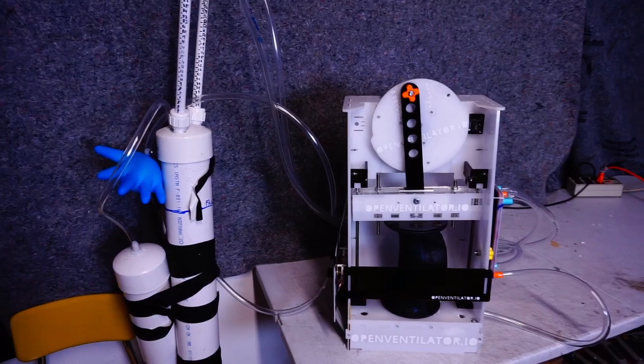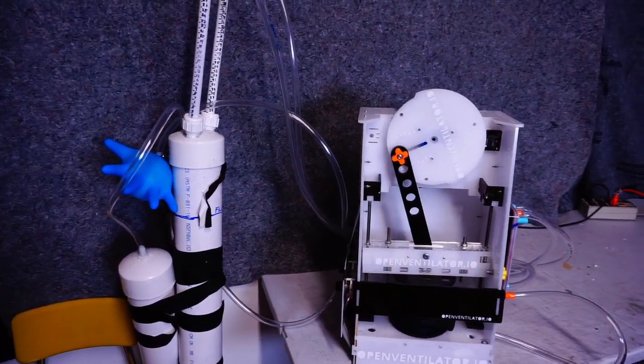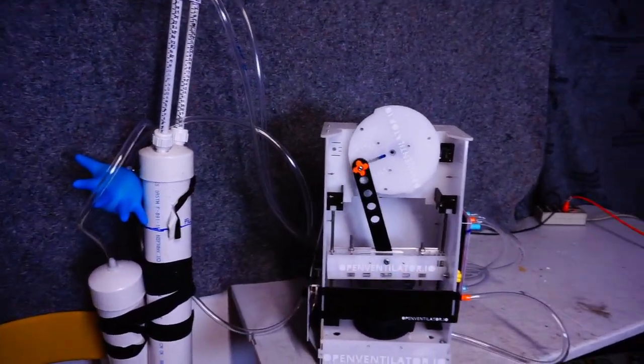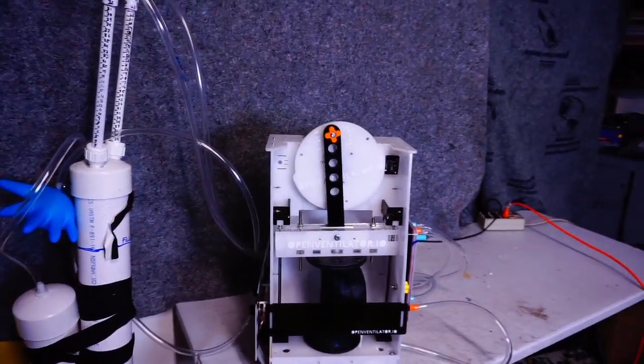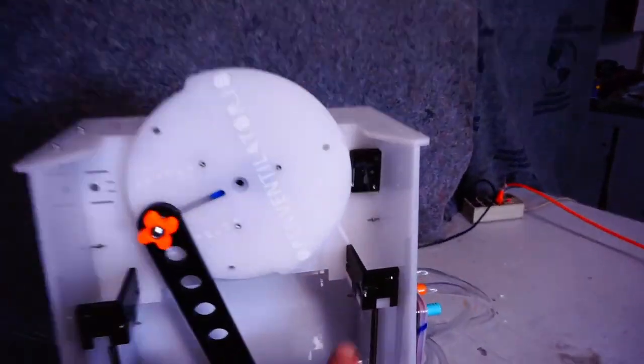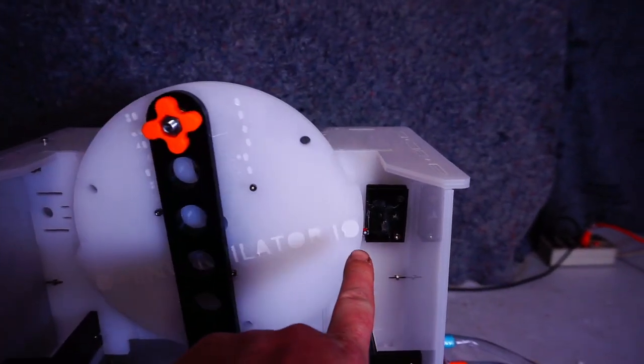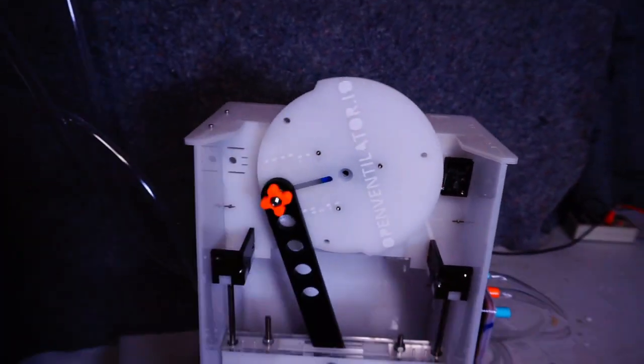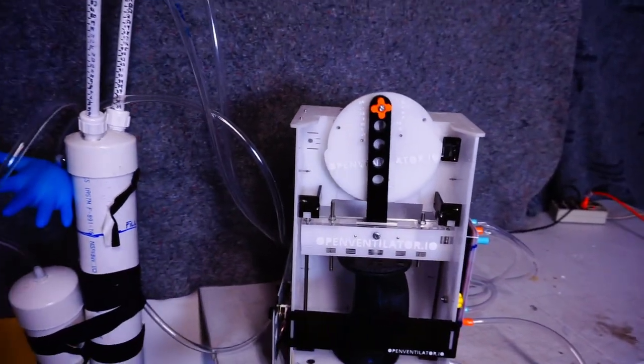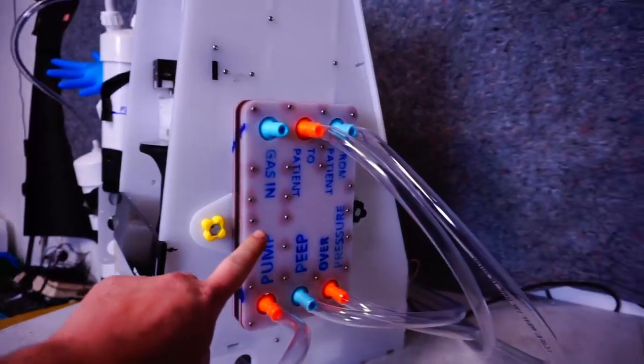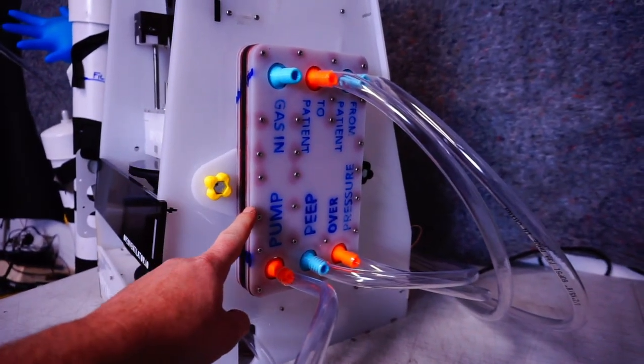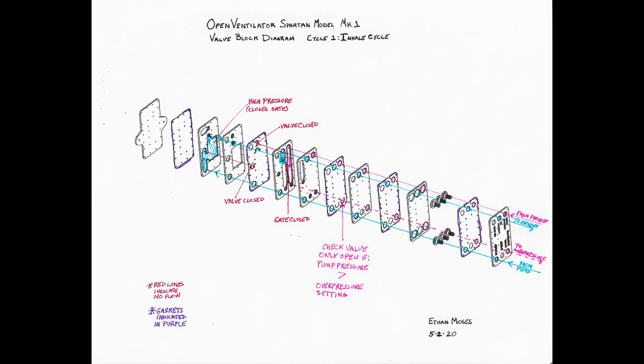the clinician or lab tester will have to actually use a chronograph like this watch here to calculate the ratio of cycle times in to out between clicks of this speed switching switch or relay, and one cycle and the next. So this right here is the heart of the machine. This is a flat pack block valve assembly. There's a whole bunch of valves integrated in here, and they do the work of the ventilator.